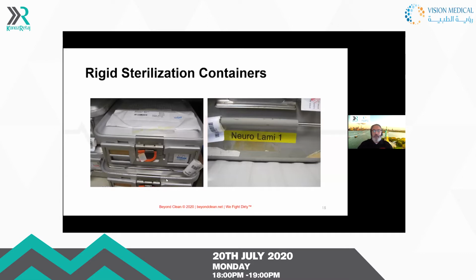And again, just some examples of what I find. This on the left is very important because this load was actually set up for a STERRAD load, and the facility had run out of STERRAD locks to place on their containers, so they used a steam lock and placed a piece of STERRAD tape over the steam indicator, which again is not a way that we should be doing that. We want to make sure we always do it correctly. More importantly, they have covered half of the vent in the top of this container, so now the sterilant cannot penetrate this device the way that it was designed. The one on the right that I always talk about is very important. We say here that if a device is not clean, it cannot be sterilized.